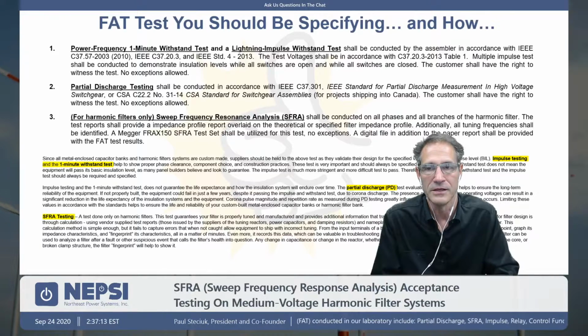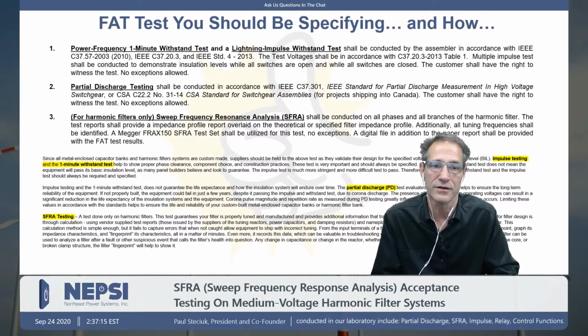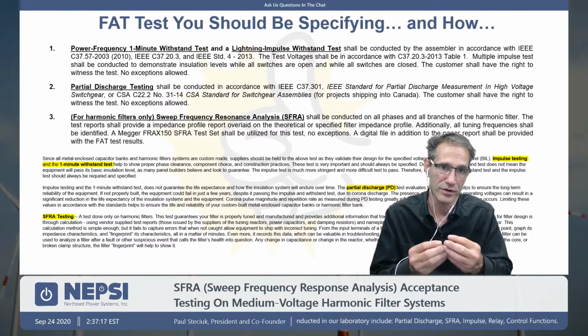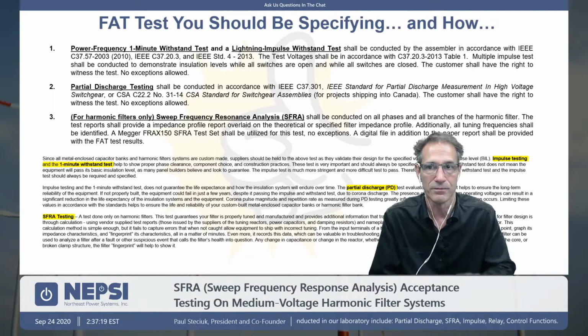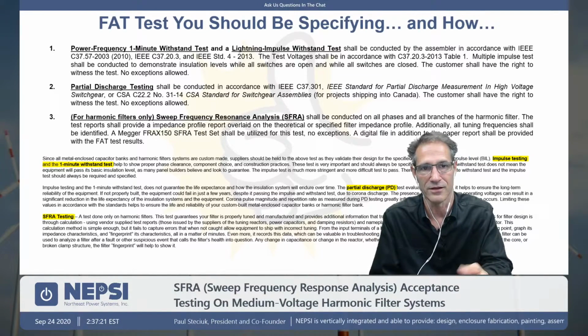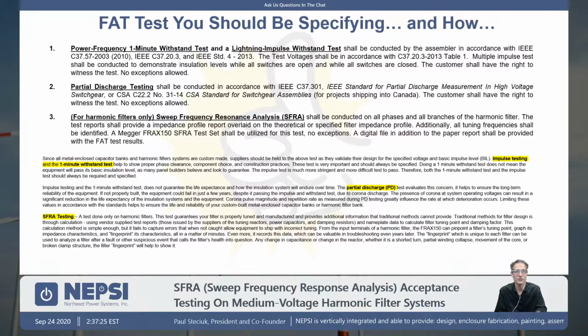Partial discharge testing helps to ensure that your equipment will have a long life. You can pass impulse, you can pass withstand, and then you can fail on partial discharge. Partial discharge measures the amount of corona discharge that you have in your design. Did you go through a barrier incorrectly? If you did, it will show up on the partial discharge test. It would pass impulse because it's a momentary thing, but partial discharge talks about the life of the equipment.